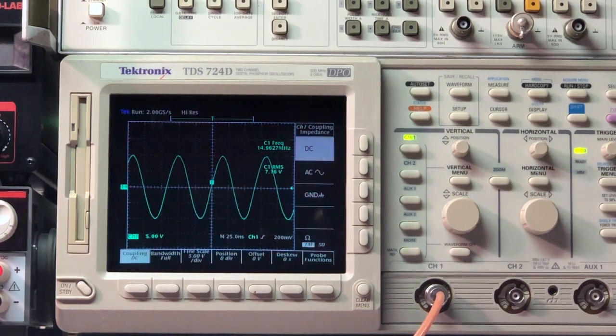So that meter looks like it's reading a little bit low still. We'll have to look at the calibration on that meter, but definitely giving us some indication and certainly giving some amplification on that signal. As you can see on the oscilloscope, it's showing 7 volts, about 7.1.